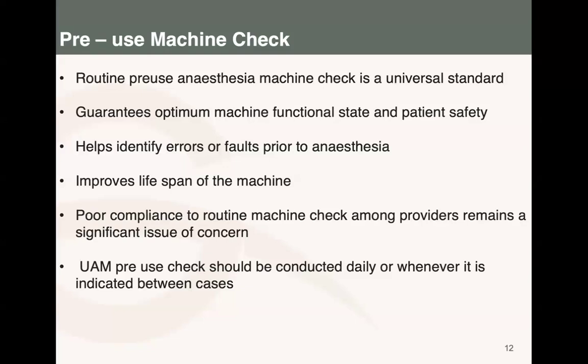Poor compliance to the check is like muting your phone while you are on call. By the time you look at your phone, you'll find there are 7 missed calls, and you have missed so many cases which could have been operated. So by not doing a machine check, you are silencing the problems, which will still be there and will keep accumulating. So we advocate that you do the machine check every morning, and also between the cases.